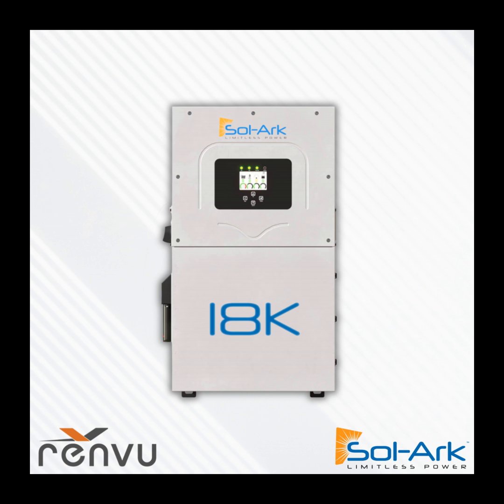So I'd strongly recommend just speccing out rapid shutdown only for your rapid shutdown devices, going with a simple rapid shutdown solution up on the rooftop, and leaving shade mitigation to your strings and multiple MPPTs on the inverter. In short, if you have a section of the solar array near the tree line, clump that together on one MPPT, and put the unshaded sections of the array on their own independent MPPTs. Industry surveys show that's just as good as having module level shade optimization, except in the most extreme circumstances.